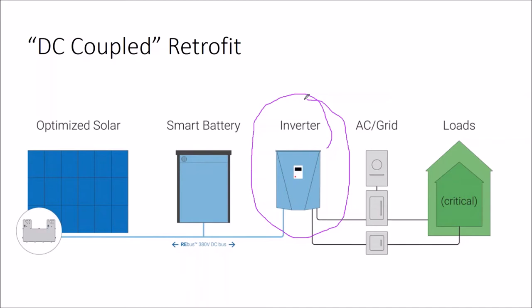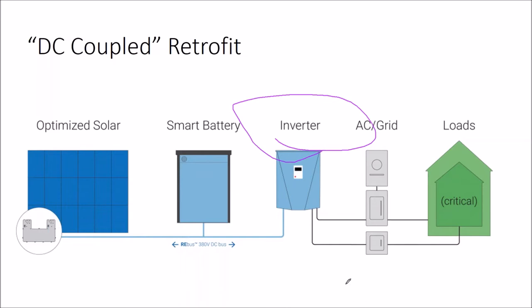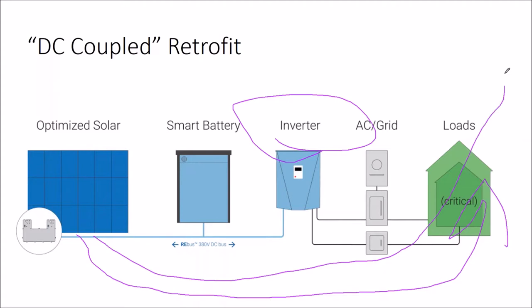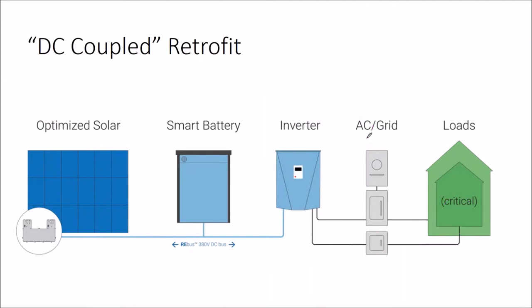So what I'm talking about is that battery inverters are less efficient than battery-less inverters. When you're using your power to go into your load, or any surplus is being sold to the grid, there's really no reason to use a battery inverter at the lower efficiency. We're talking about a 4 or 5 percent efficiency difference, so it's not the end of the world, but if you're grid-connected, you want that solar array to operate as efficiently as possible—put it on its own inverter.